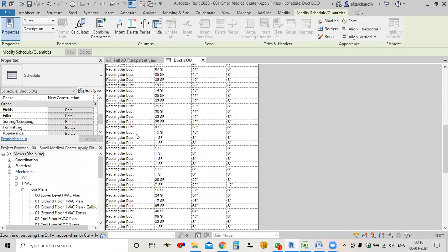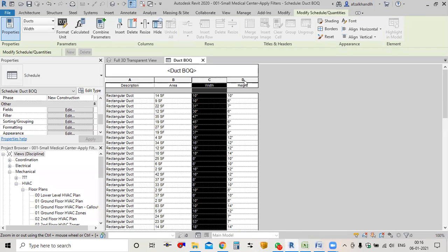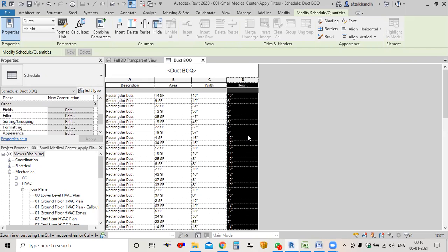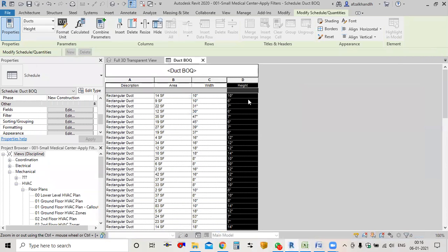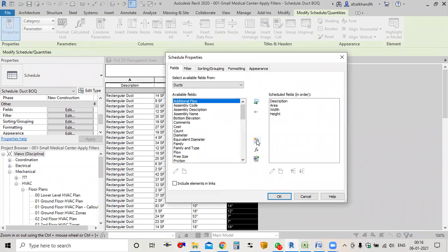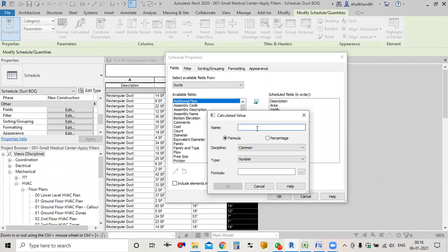In this schedule we have area, width, and height. The first new parameter I'm going to create is the maximum size, because the gauge is selected based on the maximum size of the width. From 0 to 18 inches the duct lies in gauge 26, and 18 to 30 it lies in gauge 24. So this is basically the maximum of the two dimensions. I'll first create the maximum parameter.